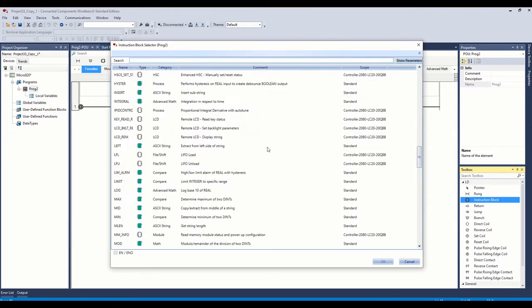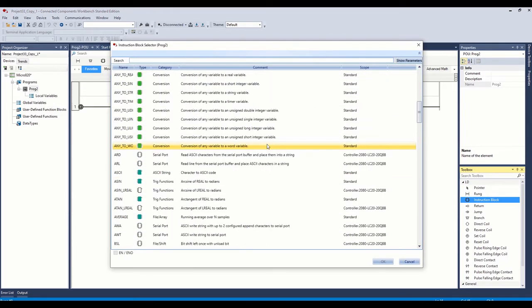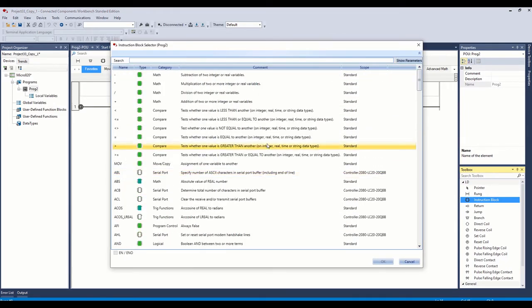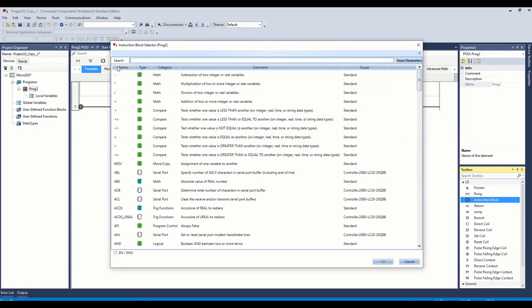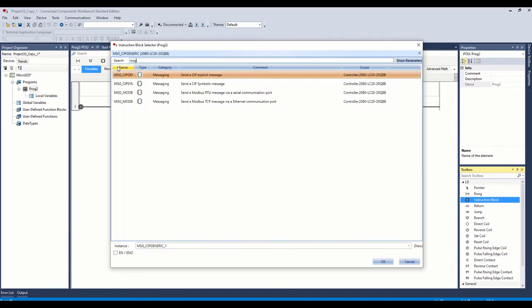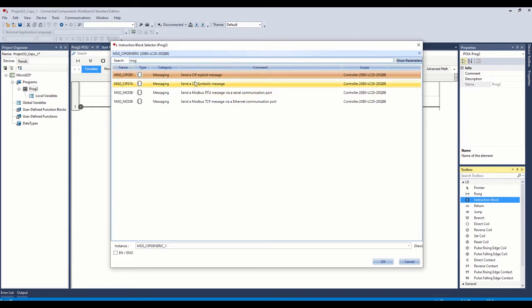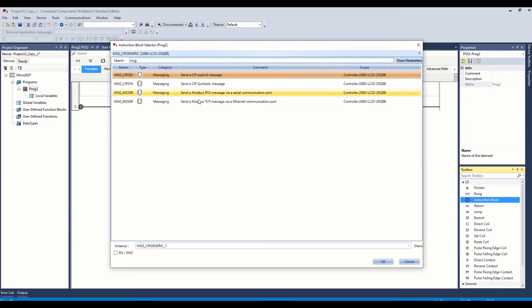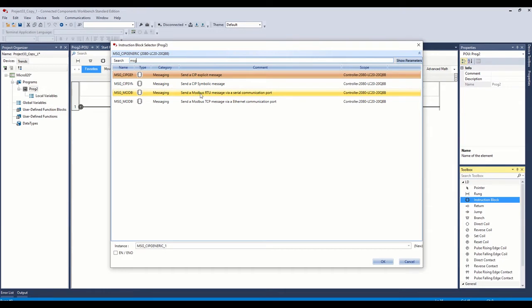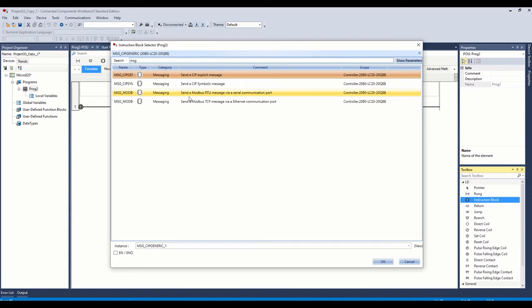Over here on the right side, we're going to click and drag this instruction block over. And then it brings up all the instruction blocks, timers, math functions, things like that that we can use this instruction block for. At the top, we're going to filter this down to just the messages. You can see we have four messages we can use. The top two are CIP messages for CIP communications. These bottom two are our Modbus. So one is Modbus RTU. We're going to use TCP for this video. But the RTU is fairly straightforward once you know how to do this TCP, and it also is covered in the programming manual. So we're just going to double-click on our TCP.